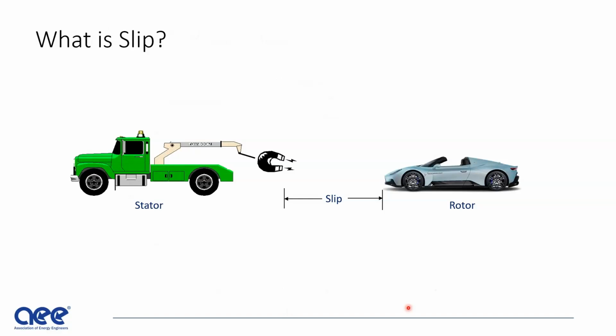And motor slip is very important. So this is just an illustration of motor slip. Basically, the motor, in this case the rotor, is always trying to chase the rotating magnetic field in the stator, and it can never get there. It can never catch up. If the car was to actually catch up to the magnet, you would lose all of your rotational energy. You want to create this drag, if you will, so that the slip is always present, and this is what keeps it rotating.